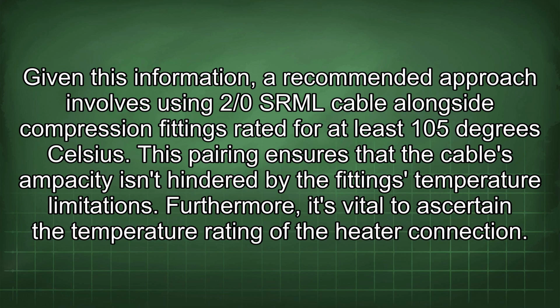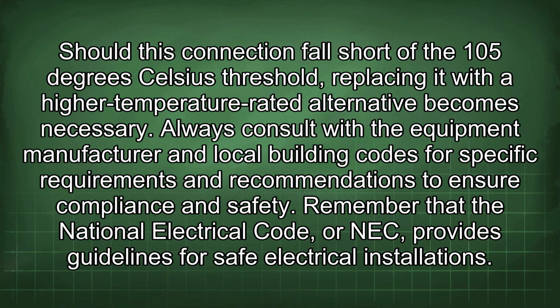Furthermore, it's vital to ascertain the temperature rating of the heater connection. Should this connection fall short of the 105 degrees Celsius threshold, replacing it with a higher temperature rated alternative becomes necessary. Always consult with the equipment manufacturer and local building codes for specific requirements and recommendations to ensure compliance and safety.